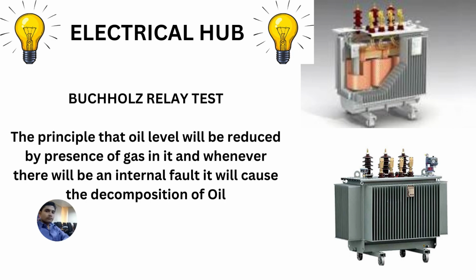That heat will break the insulation of the oil, or even any solid insulation. Then, due to the decomposition of the oil, gas will be formed. That gas will try to move towards the conservator. While moving towards the conservator, it will get trapped in the Buchholz relay. When there is an accumulation of gas in the Buchholz relay, the level of the oil will drop, so it will cause an alarm or tripping.